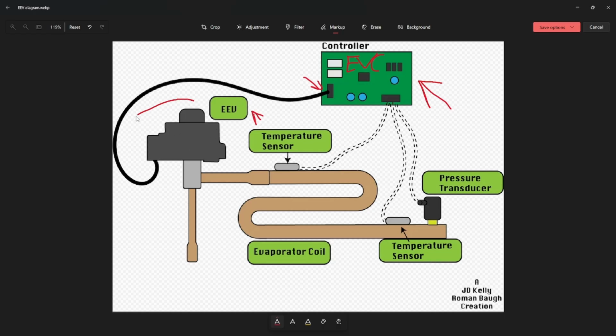So this piece of the EEV that has your wire going to it is known as a stepper motor. It is a DC volt stepper motor that receives pulse signals from the control board to drive the needle inside the valve up or down. That up or down action is what controls the orifice in this cavity that actually opens or restricts refrigerant flow into our evaporator coil.